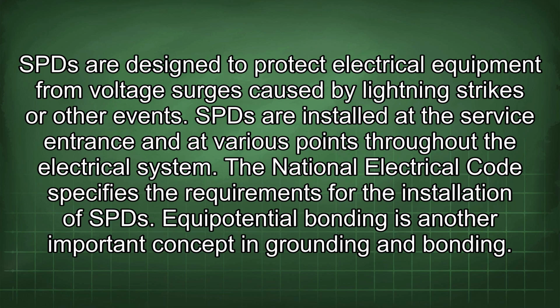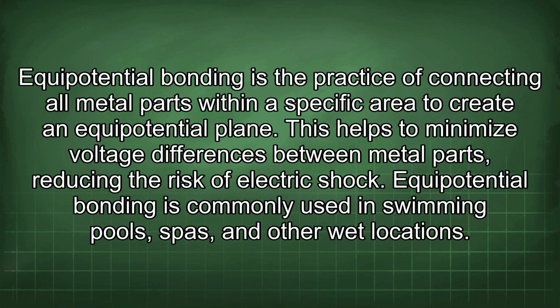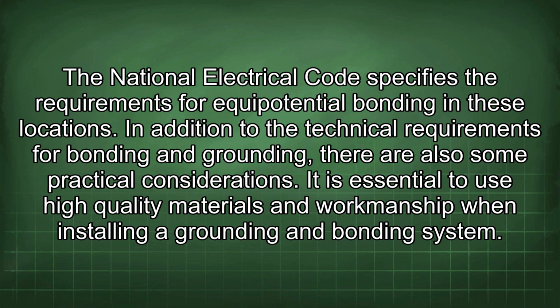Equipotential bonding is another important concept in grounding and bonding. Equipotential bonding is the practice of connecting all metal parts within a specific area to create an equipotential plane. This helps to minimize voltage differences between metal parts, reducing the risk of electric shock. Equipotential bonding is commonly used in swimming pools, spas, and other wet locations. The National Electrical Code specifies the requirements for equipotential bonding in these locations.